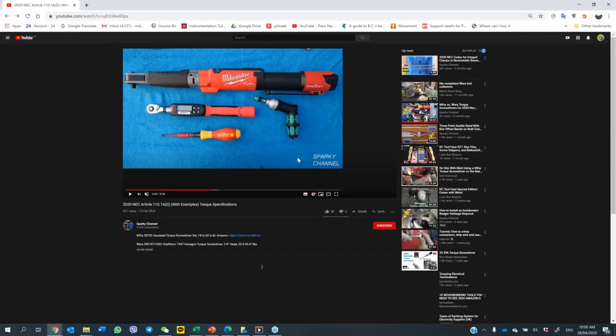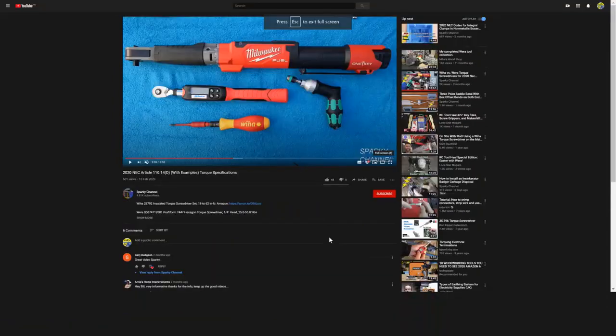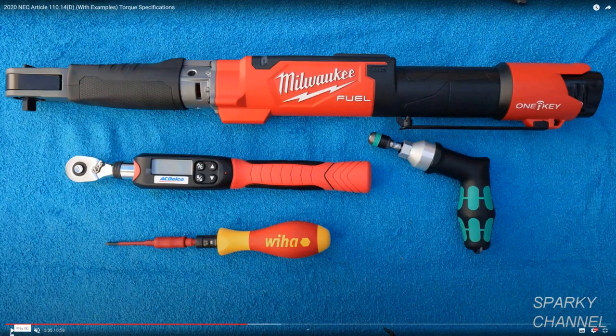Now what I'm going to show you is, have you considered torquing standard? So if you were to compare how you do torquing, if you're not using a torque screwdriver or a torque wrench, are you doing a quality installation? Certainly not. If these tools that you see on the screen here were utilized, not everybody uses them. They're great tools, but they're expensive. So a torque screwdriver, not every technician has to have them. You can implement into your quality management system where the lead or the one QA/QC guy goes through and checks for tightness of all terminals using that tool.